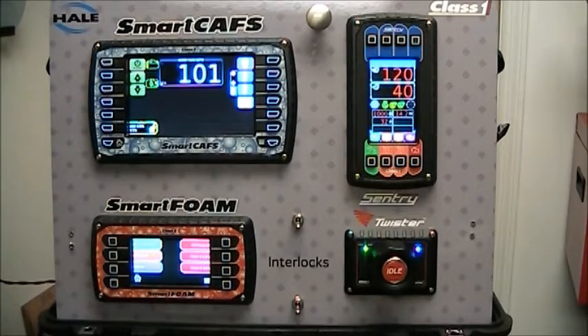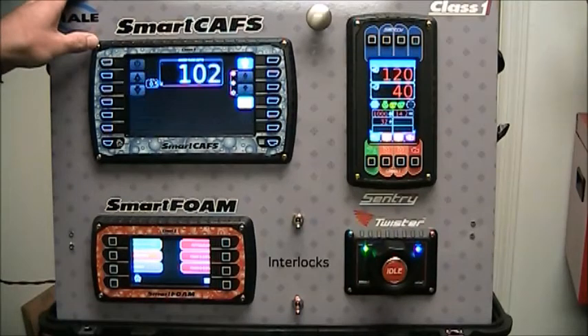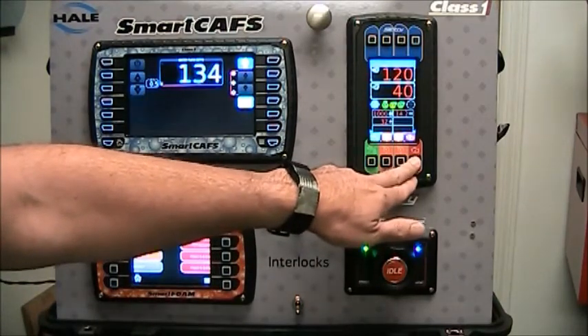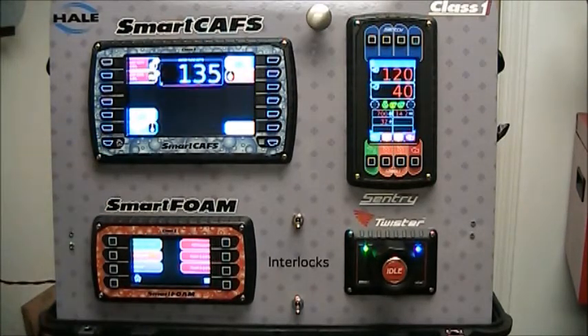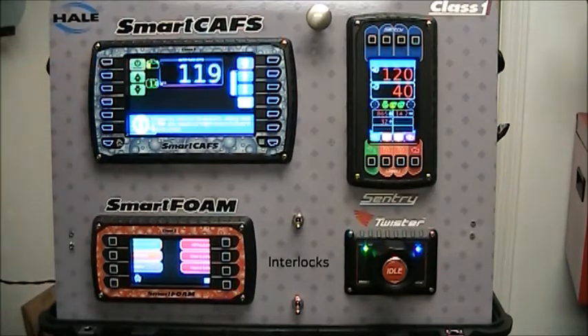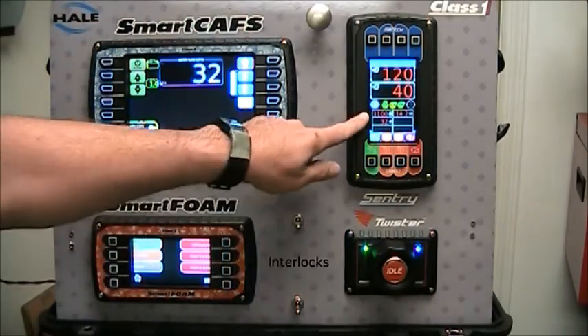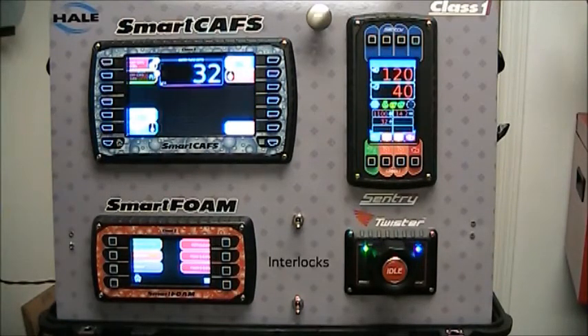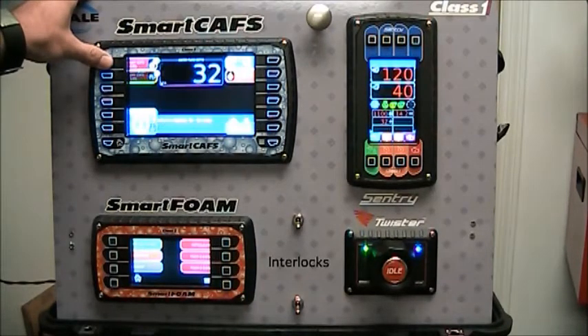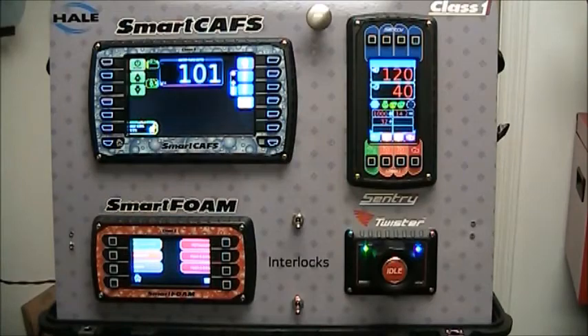To recap the simplicity of the system: turn off the SmartCAFS system by pressing the foam button, which turns off the foam and the air. Press the idle button on the Sentry to bring the engine RPM down to idle. Press the home button to go back to the preset page and select any preset. It goes from the preset page to the operation page, activates foam and air, and communicates with the Sentry Governor to ramp up to the engine RPM dictated by that preset — and it's ready to operate. Selecting a new preset is as simple as pressing the home button, moving back to the preset page, selecting a new preset, and it sets the foam and air and communicates with the governor to ramp up to the RPM set for that preset.